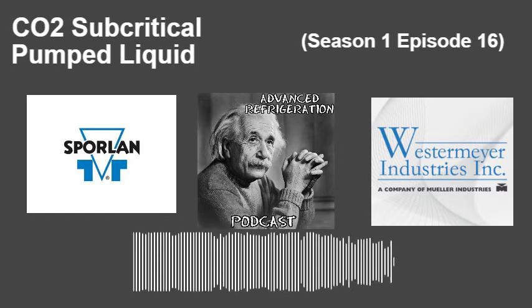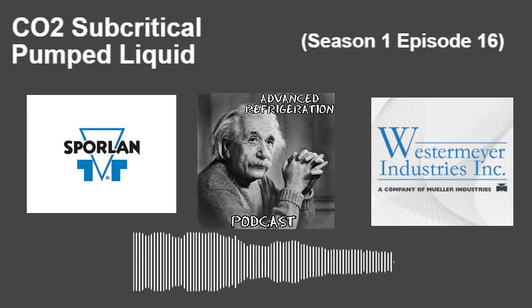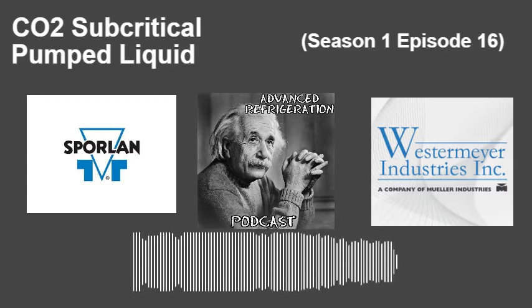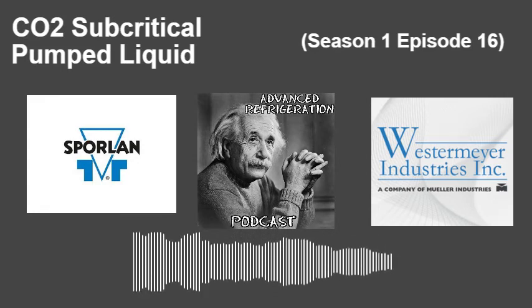So what he was talking about before, the suction on this, it doesn't usually say suction on there. It usually just says return, because like he said, it's called a wet suction, basically a little bit of liquid, a little bit of vapor coming back. There is no expansion device in these things. All there is, basically, is just a distributor, and that's just to distribute the refrigerant evenly. Sometimes you won't even have an actual distributor. Sometimes it'll just be one line in, one line out, comparable to a glycol coil.